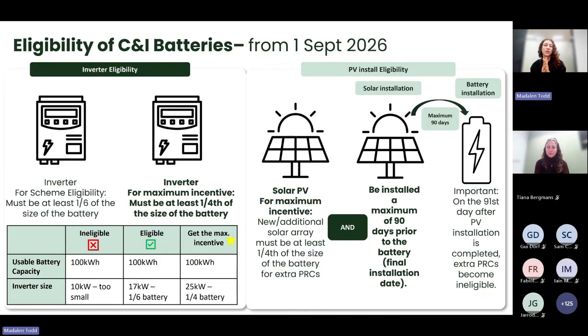As I mentioned, I'm going to go through some of the important requirements around the inverter and PV solar array sizes that are relevant whether you're installing in an apartment block or a smaller or larger commercial premises. All battery installations have to comply with these inverter sizes and the PV sizes. First I'll talk about the inverter eligibility. The size of the inverter that you install with the battery for the peak demand reduction scheme must be at least 1/6 of the battery's usable capacity to be eligible.